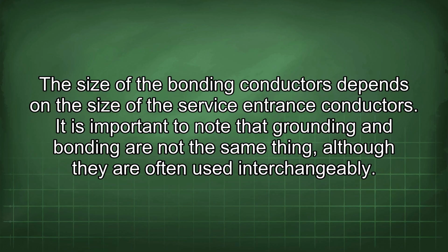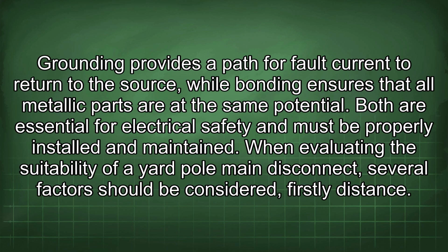It is important to note that grounding and bonding are not the same thing, although they are often used interchangeably. Grounding provides a path for fault current to return to the source, while bonding ensures that all metallic parts are at the same potential. Both are essential for electrical safety and must be properly installed and maintained.